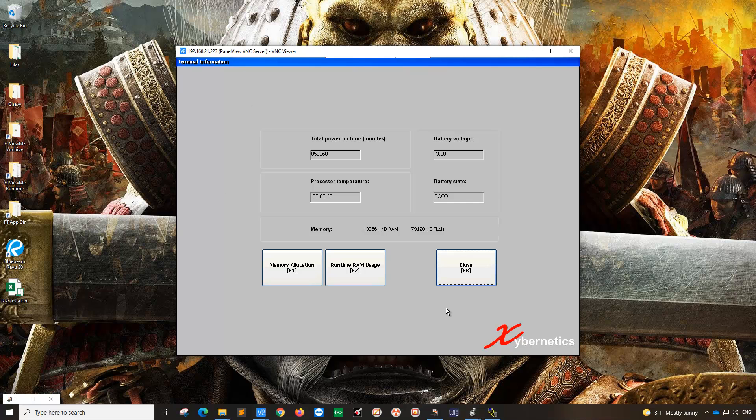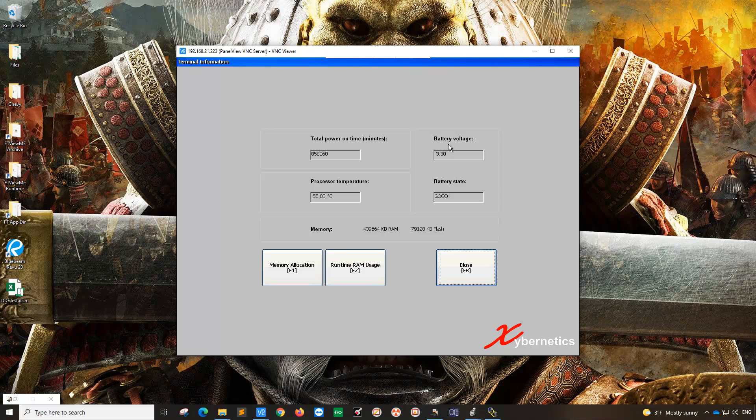In this section here, it shows you how much time it's been running in minutes on the top left hand corner. On the right hand column here, it shows you the battery voltage. This PanelView is less than a year old, so the battery voltage is relatively good at 3.3 volts.